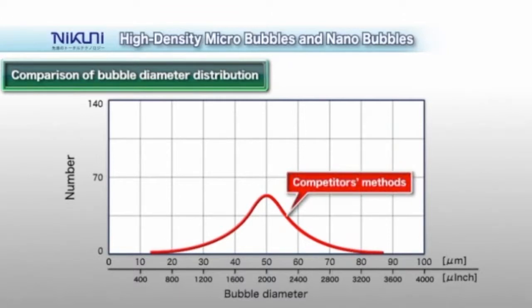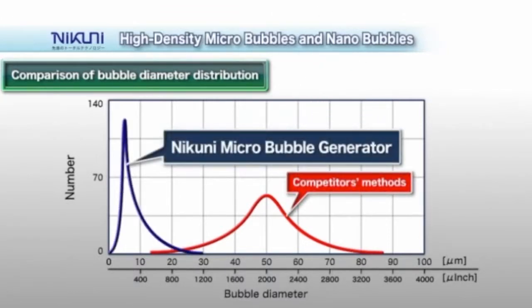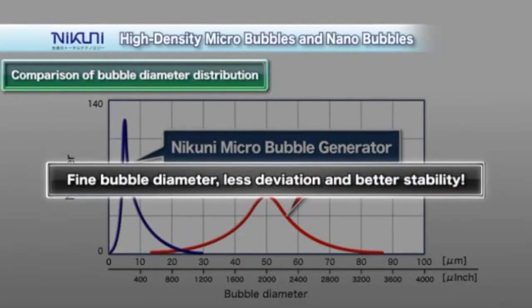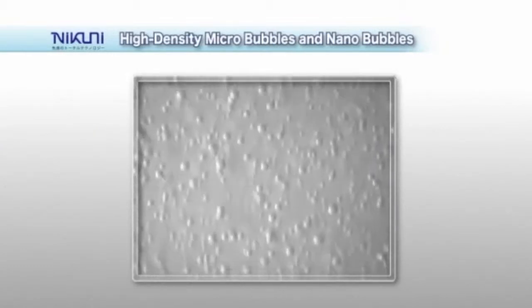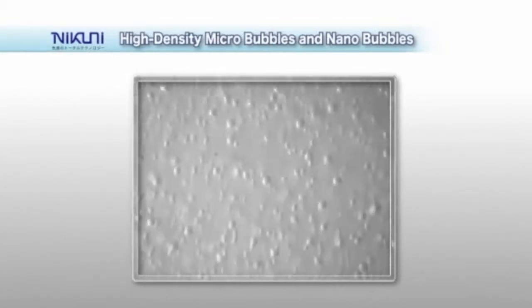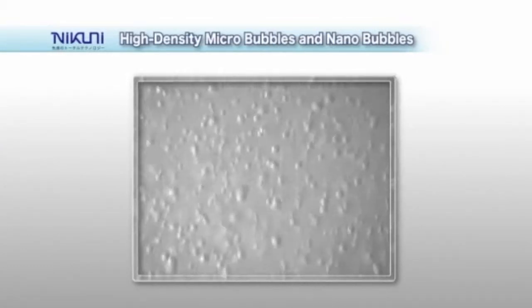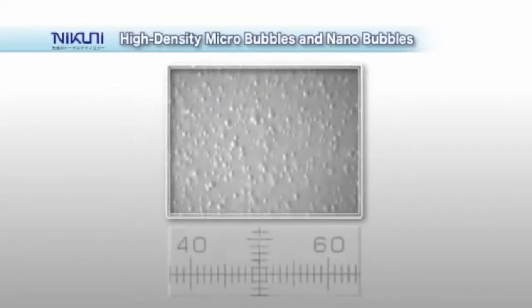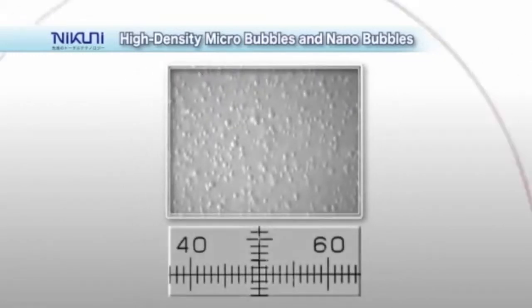Nikuni micro nano bubbles have a mean diameter of approximately 5 microns with little deviation. The tiny micro nano bubbles adhere to fine suspended matter in the water and bring them to the surface, allowing for improved cleaning performance.